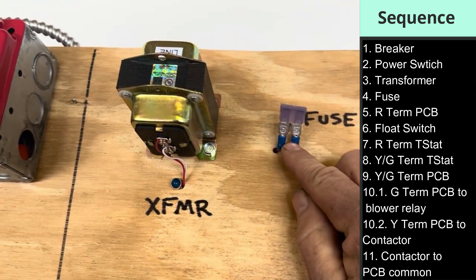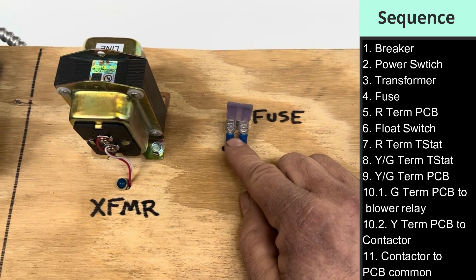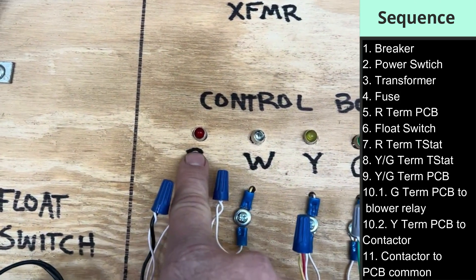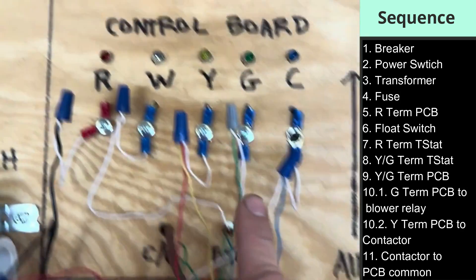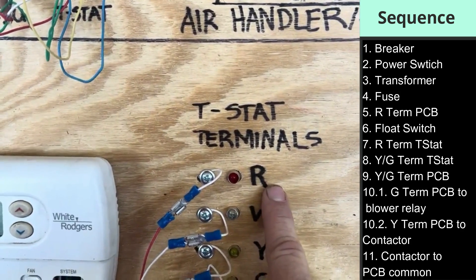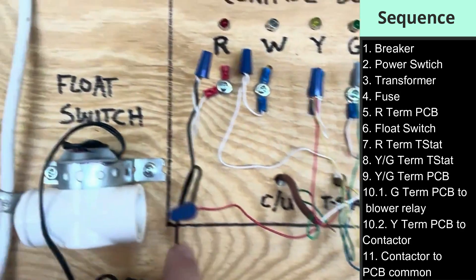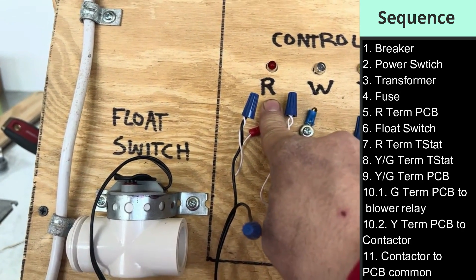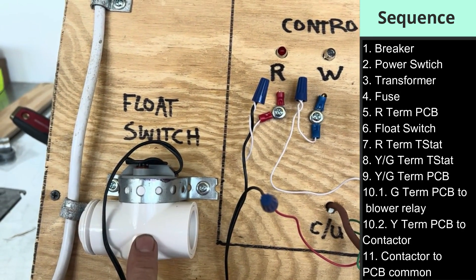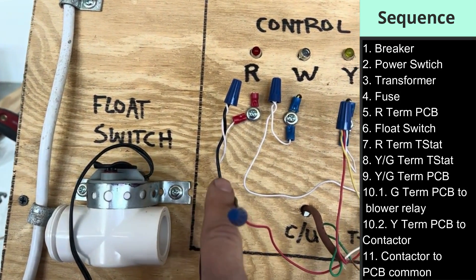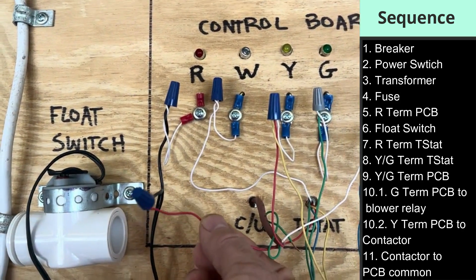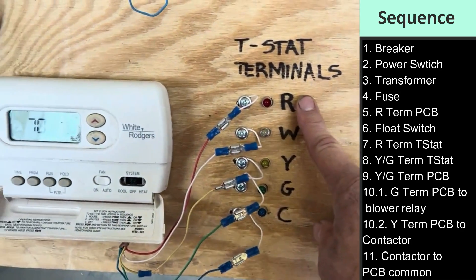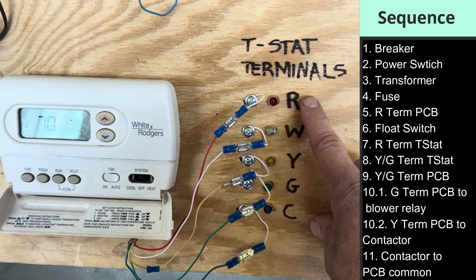From the transformer it's going to go through a fuse — this is going to be a 3 or 5 amp fuse, most often located right on the control board. Once that 24 volts goes through the fuse, it comes to the R terminal on our control board. From there it usually goes straight to the R terminal on our thermostat, but a lot of systems are going to have a float switch in between. The 24 volts comes off the R terminal on the control board, goes into one wire of the float switch, through the float switch, out the other wire, and then travels down the red wire to the R terminal on our thermostat.